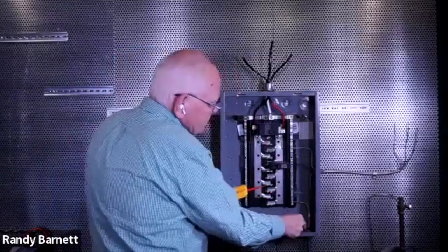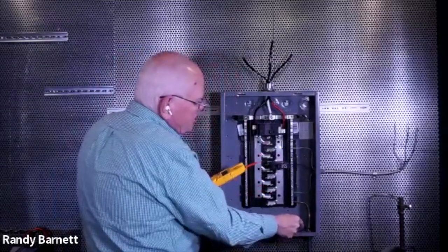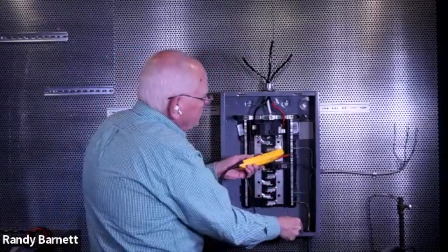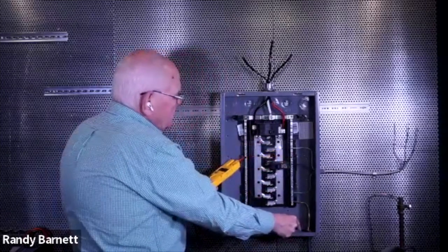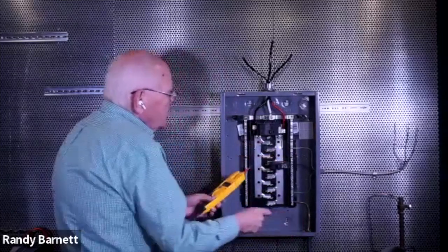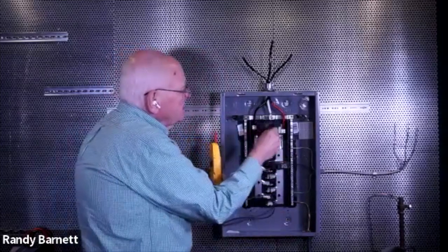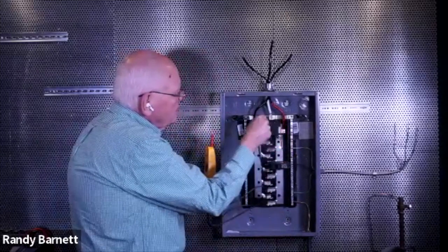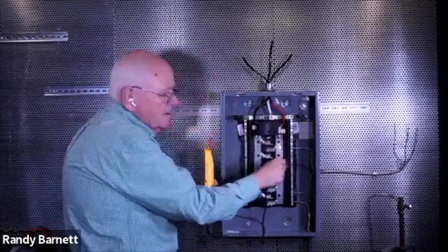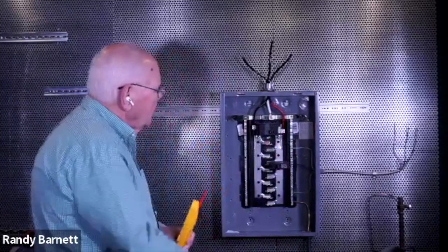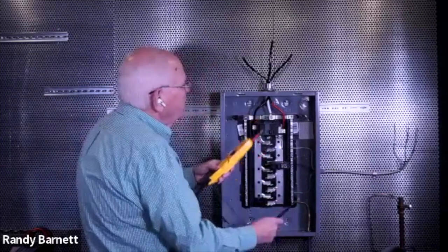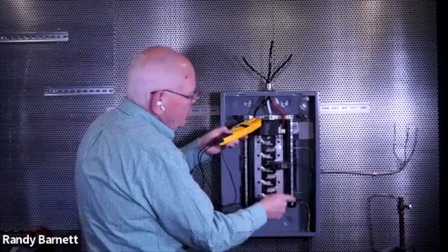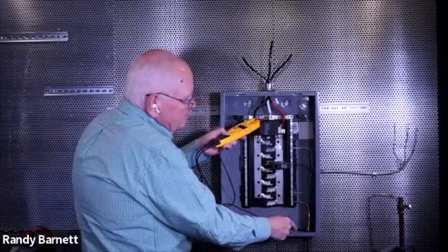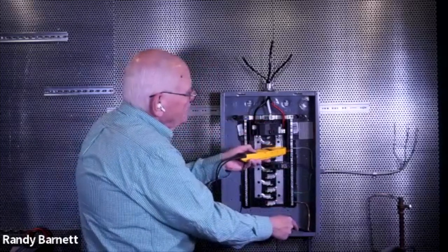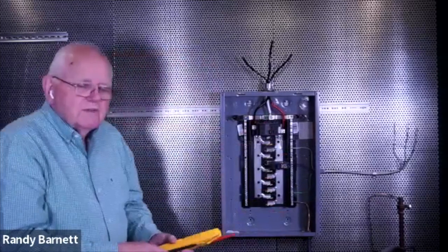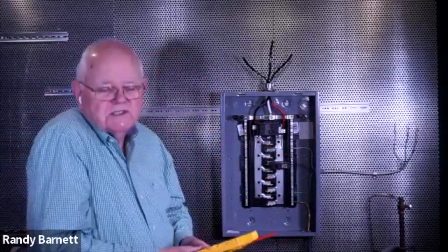So when I put one test lead on my connector right here from my MT, which is screwed into the cabinet, and touch the bus bar, my meter beeps. I get 0 ohms. The same is true here on the left. If you look at the construction here, you can see that the bus bar goes across the top and ties into a bus bar on the left as well as the right-hand side. If I were to unscrew the green screw, I wouldn't have the continuity between the metal frame of my enclosure and my neutral bus bar. So 250.28 talks about the main and system bonding jumpers.